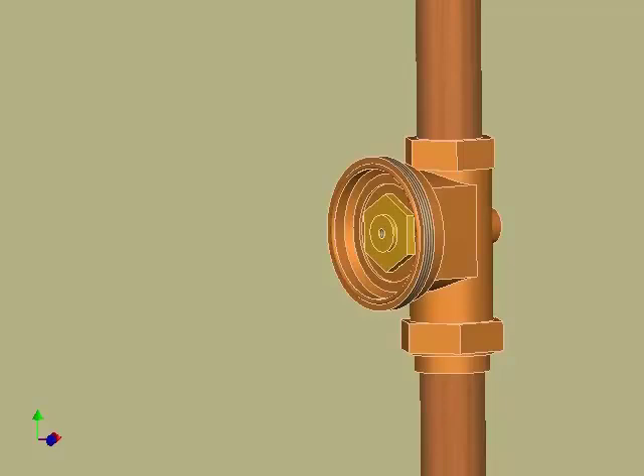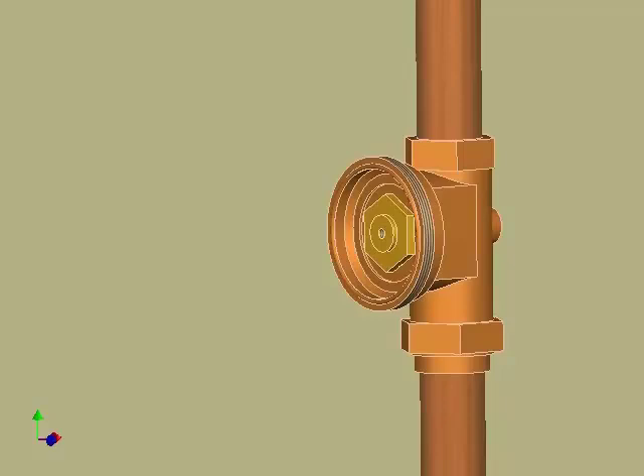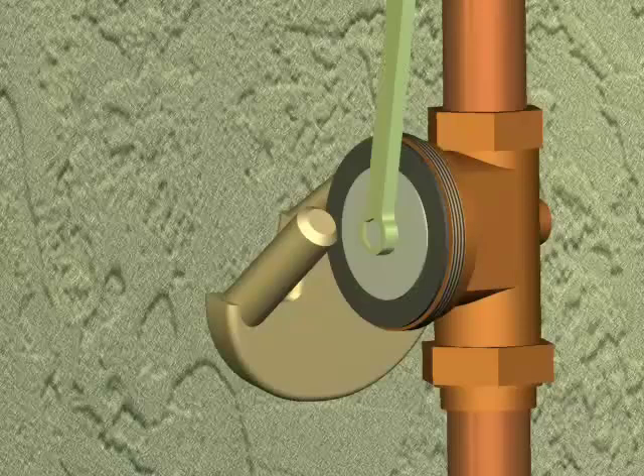Any sharp burr can cut the diaphragm. Install your new diaphragm, diaphragm disc, and diaphragm bolt. You will hold the diaphragm against the edge of the body to keep it from rotating. Tighten your diaphragm bolt securely to prevent leaks into the bell.